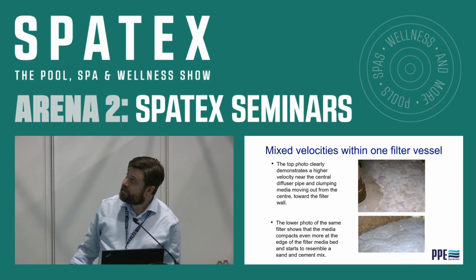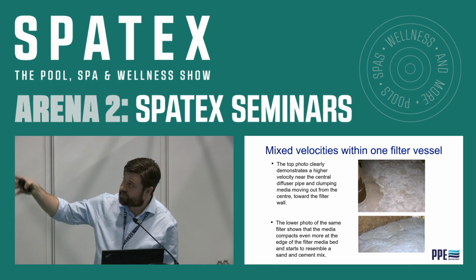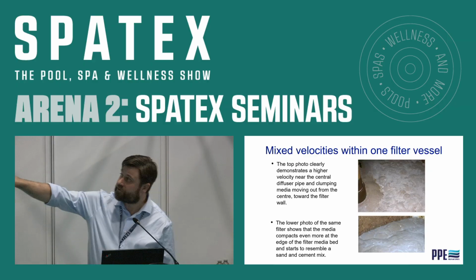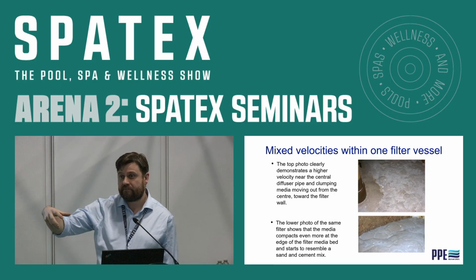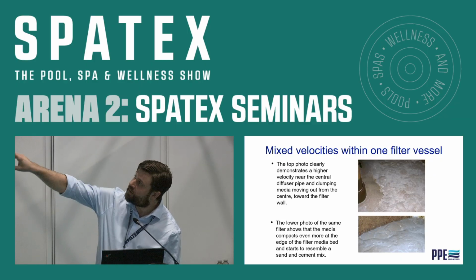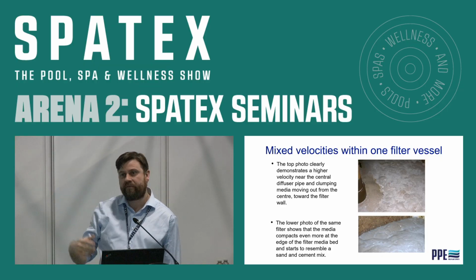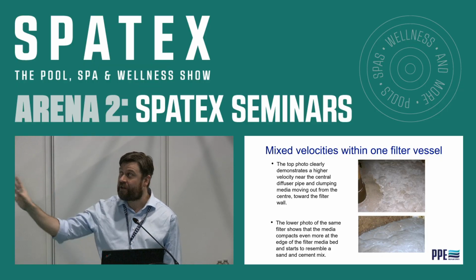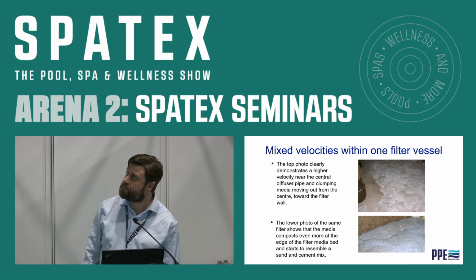Other things that we can see is where the water is traveling at a high velocity through the center of the filter, which is this part just here, what we've actually got is high rate. So the flock's not going to settle at all, and the water's going straight down through the middle, down to the laterals. And as you make your way out to the sides, this is the same filter, you can see it solidifies more and more as the velocity becomes less and less, and there's no flow at all, and you've just got dead spots around the edge of the filter. Okay.